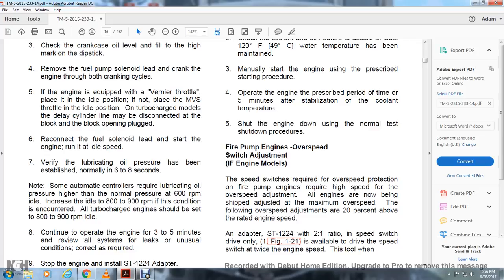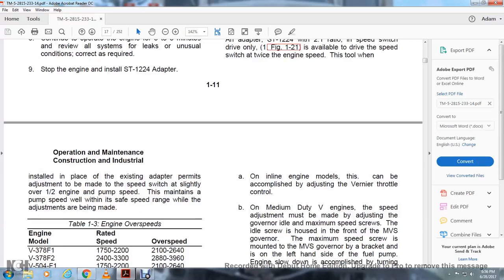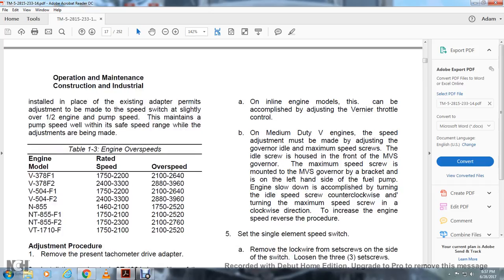An adapter, ST1224, with a 2-to-1 ratio speed switch drive, shown in figure 121, is available to drive the switch at twice the engine speed. When installed in place of the existing adapter, this tool permits the speed adjustment to be made at slightly over half the engine and pump speed, which maintains the pump speed well within the safe speed range while the adjustments are being made.